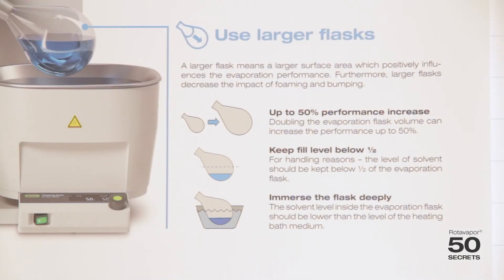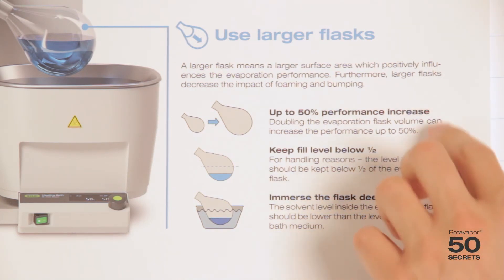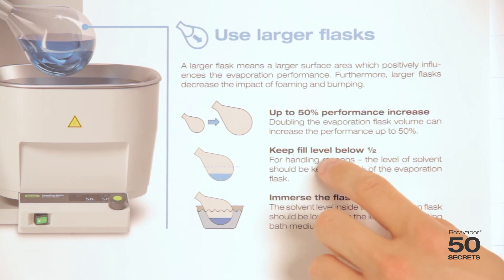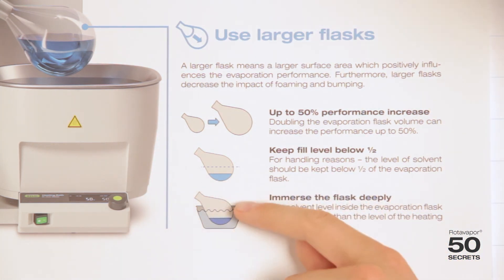The fifth secret is about using larger evaporating flasks. It's very important that this can impact the performance quite dramatically. You should keep the fill level below one half and you should make sure that the flask is immersed deeply into the heating bath.